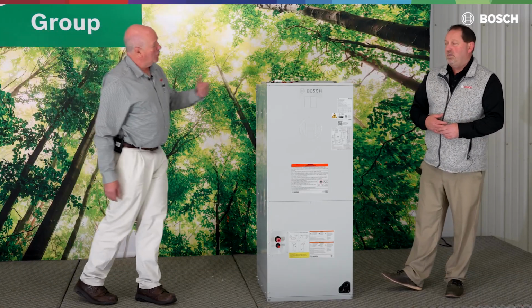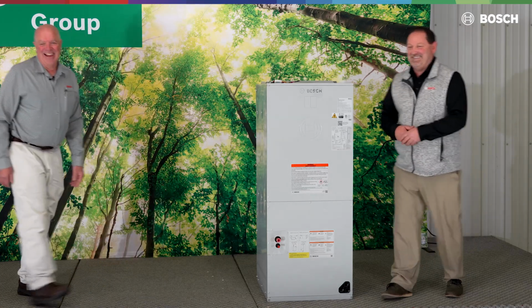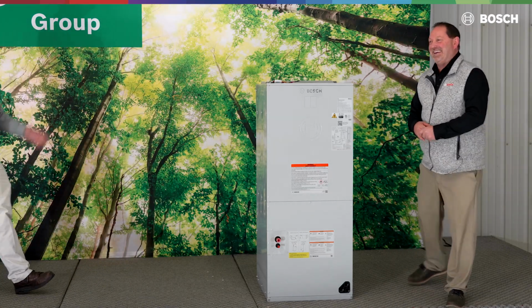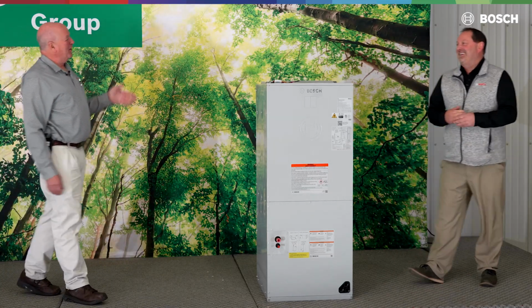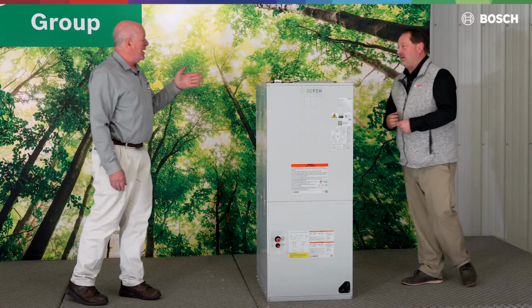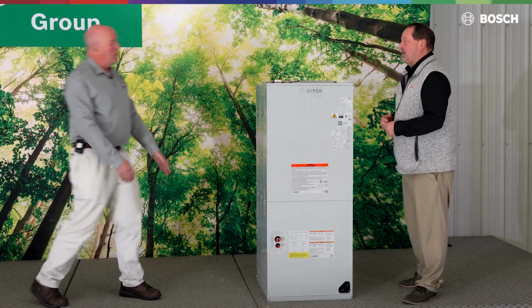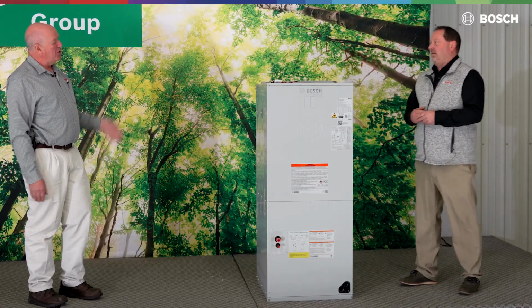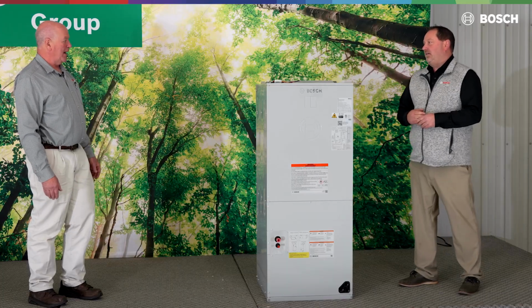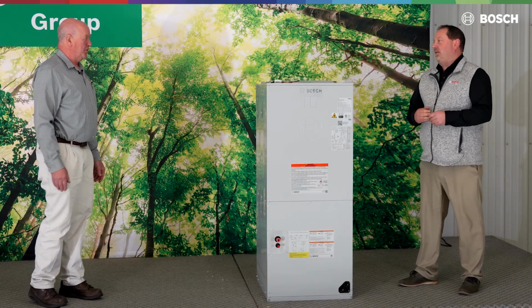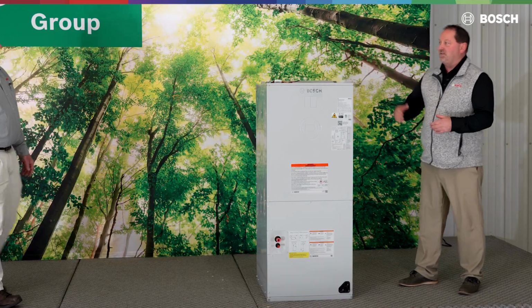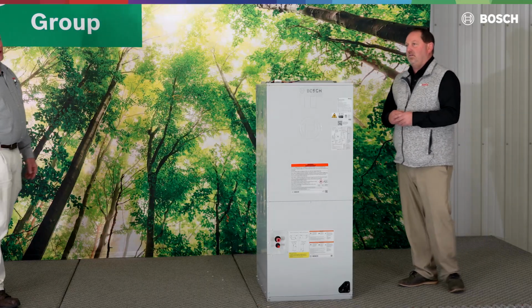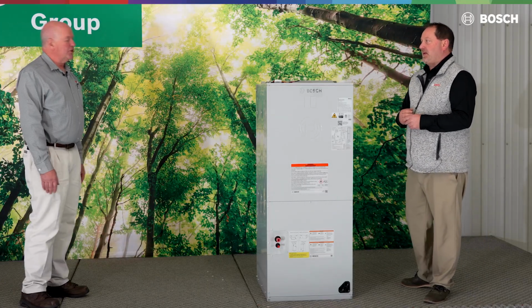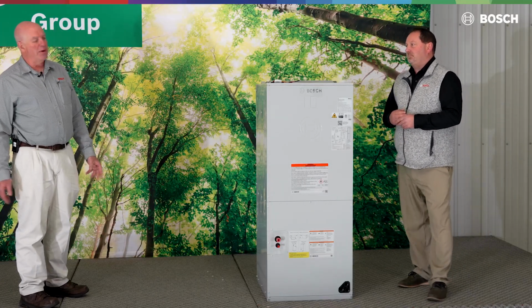So what happens after -13? It goes to -14. If there's a call for heat, it'll complete the call. Okay. Even to -15 or -20. Okay. But when the thermostat is satisfied, that unit will not start back up until it gets above -13. The unit will not come back on until it gets above that -13. So that's sometimes an issue concerning your location. If it never gets that cold, that's not an issue.